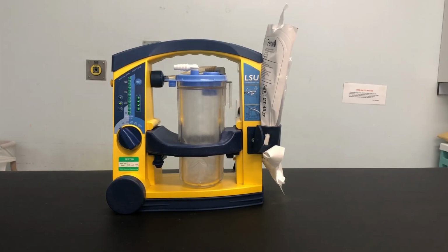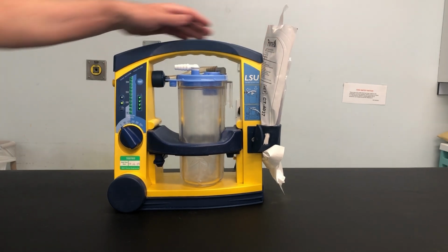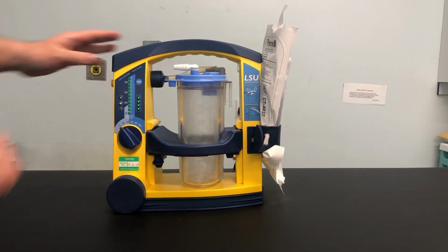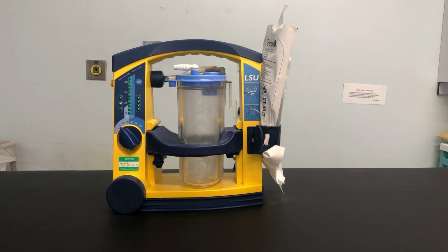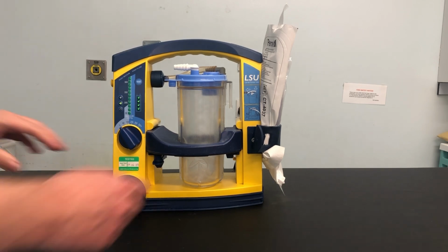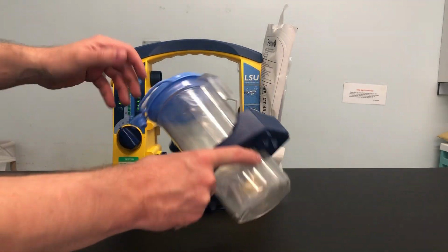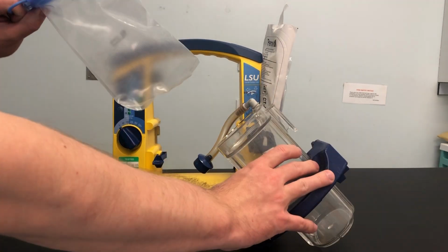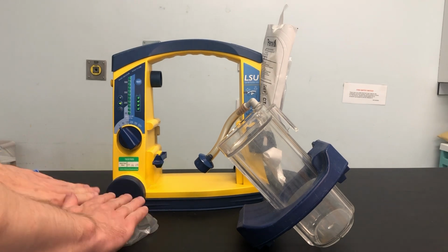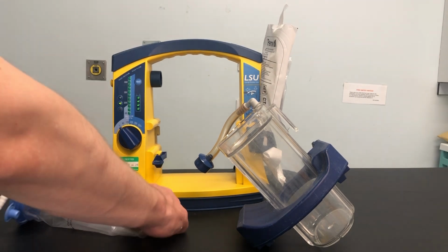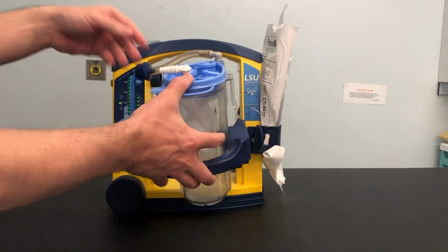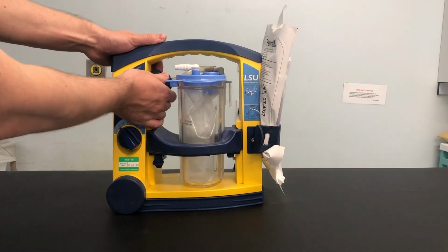If the device has passed its daily test, please ensure that the device is connected to the mains power and the mains power is turned on to ensure the device is ready to be used when required. If the device fails, remove the canister and liner, check for damage and replace the liner if necessary. Check all the components and reassemble. Run the test again, and if it fails again, remove the LSU from use.